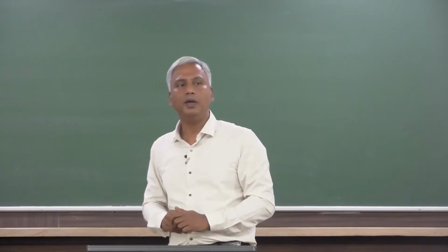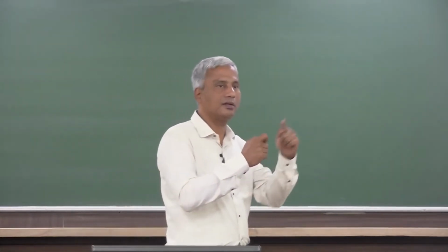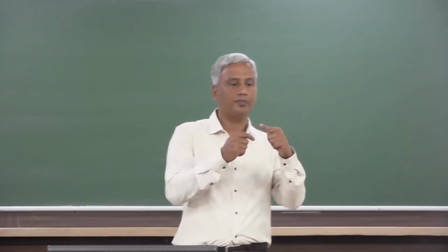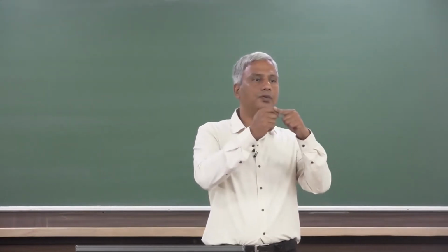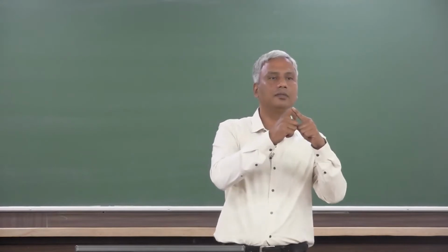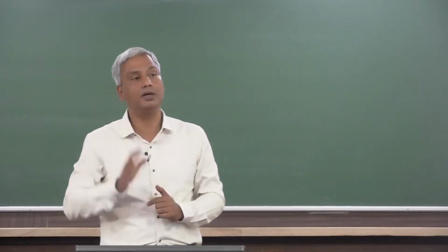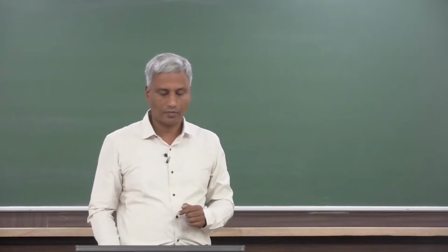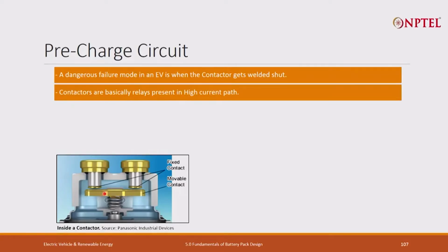When huge inrush current flows, many times what happens? The contactor is nothing but two conductors and a mechanism to connect the path. If huge current flows, this path gets welded in, and if it is welded in, when you want to disconnect, it won't get disconnected. So it's a problem. So what you have is a spring loaded contactor, and this spring loaded contactor is activated using the BMS signal. If there is a huge inrush of current, these two terminals, this is the connection between the contactor and the outside. Now if this gets welded because of the huge current, then you cannot disconnect it when needed. So you don't want this type of situation.